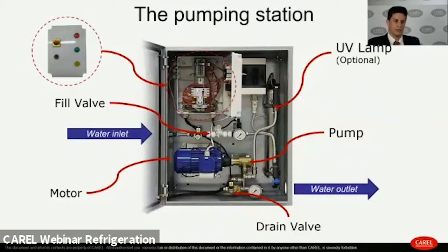The pumping station, thanks to its features, can be flexibly installed, since the IP rating can guarantee installation also outside. So we don't necessarily need a technical room where to install the pumping station. And this allows flexibility in terms of installation, since usually condensers and gas coolers are placed on the roof of the building. So we are able to install the pumping station close to them, avoiding any extra cost related to complex installation.